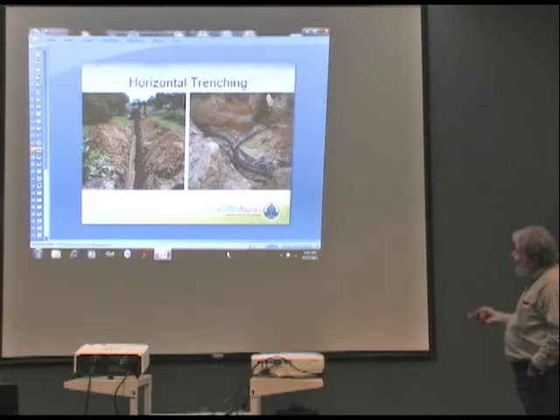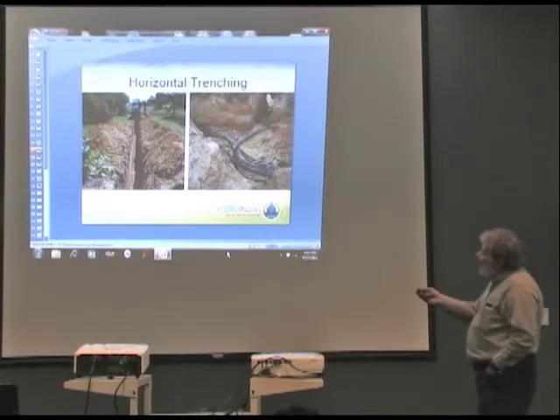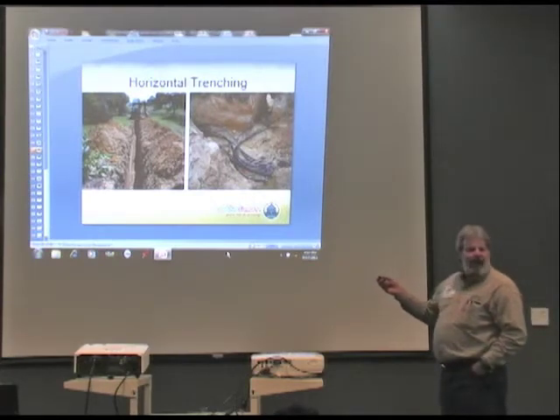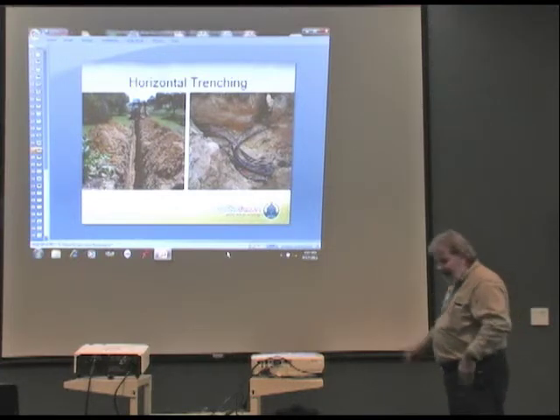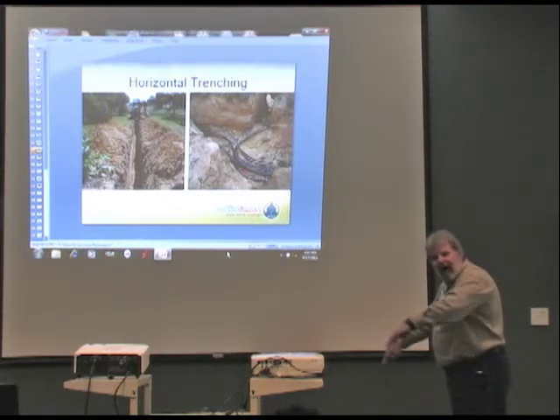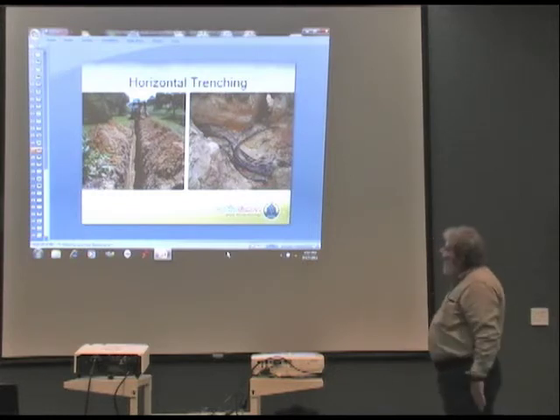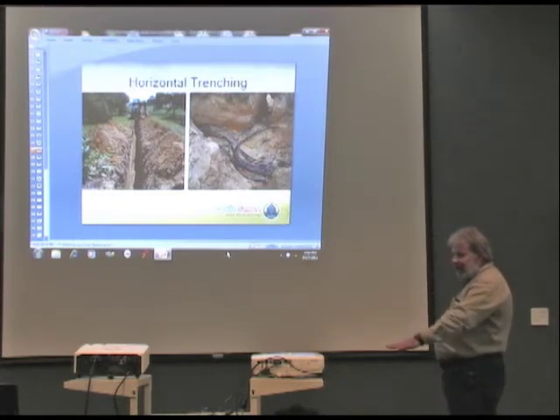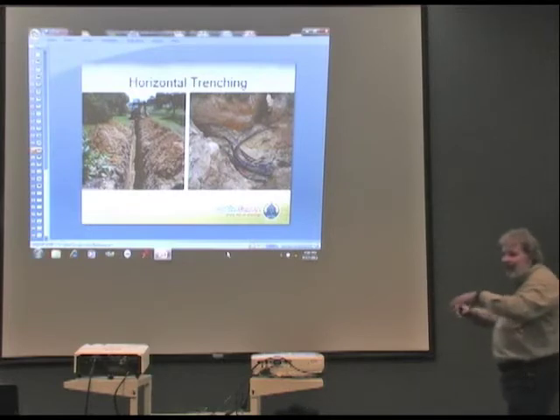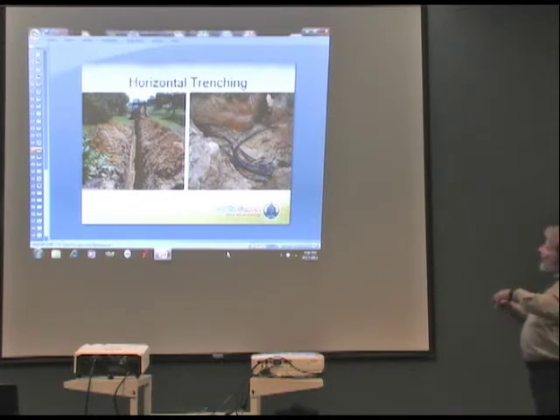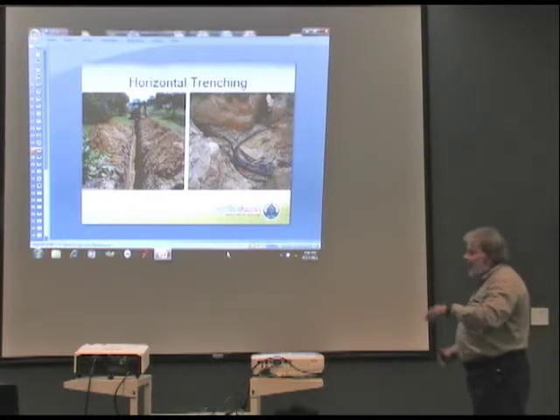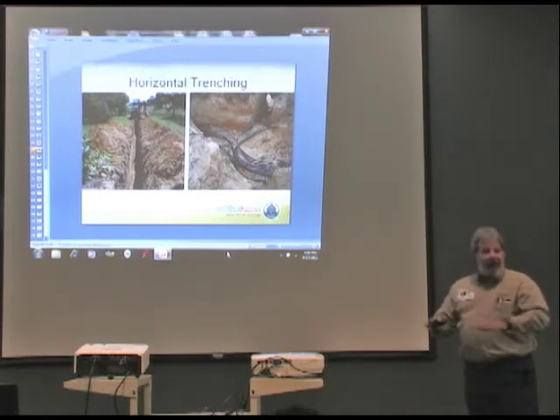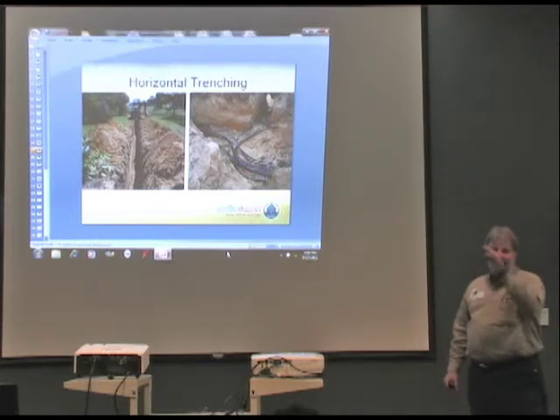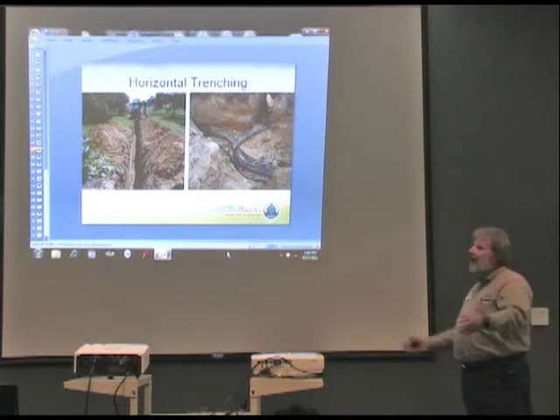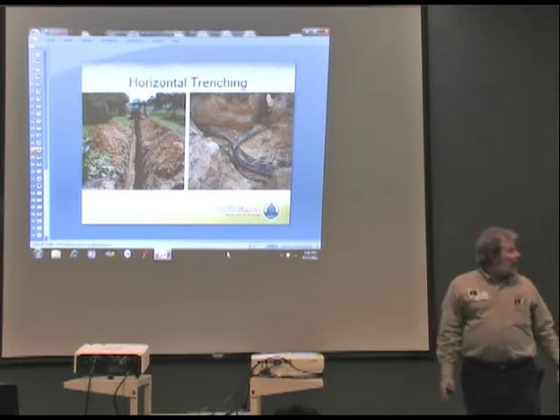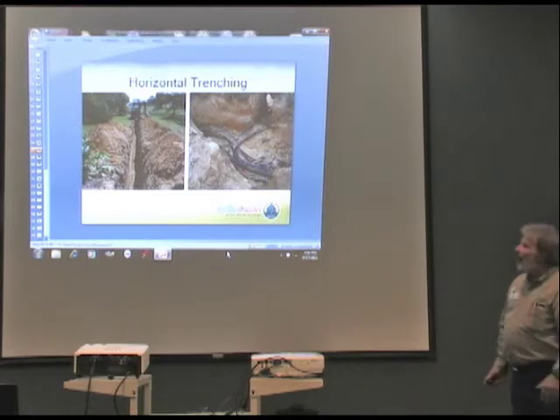Now this is horizontal. We go 5 or 6 feet deep, depending on the amount of land I have. The pipes go on the side and come out on the bottom — they're staked on the sides. One is on the bottom, the next is about 2 feet above, and then it's backfilled in. The excavator, with us always there, has to bucket that in carefully. I can't have the pipes getting knocked off, no wavy pipes — not good, I want them straight. Once we get above the pipe level, they can push their stuff in wherever they want, no problem.